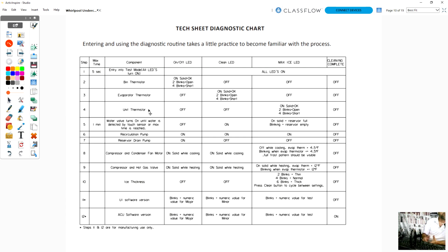Now, if you think that the evaporator thermistor or the bin thermistor is bad, it's just as easy to go into diagnostic and test those thermistors right from the user interface than having to take it apart and put an ohm meter on those components. So this diagnostic is good, but remember, you don't need to go through every step to test the ice machine out. Just find what your problem is with the ice machine and go into that step and test that.